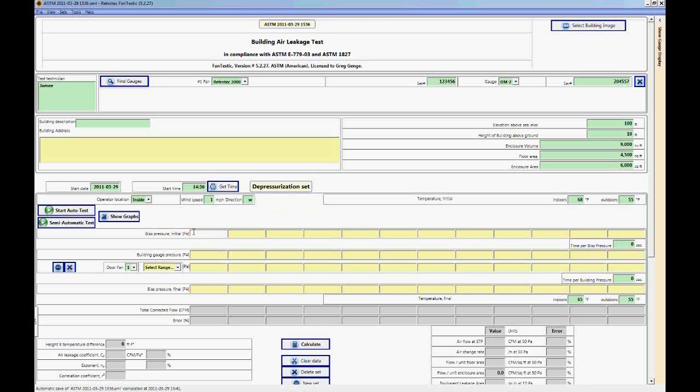Now this is the location where we'll enter our bias pressures. And to take a bias pressure when you're in the field, you can either use the baseline feature on our gauge or you can set the gauge up to read a time average of approximately 20 seconds.